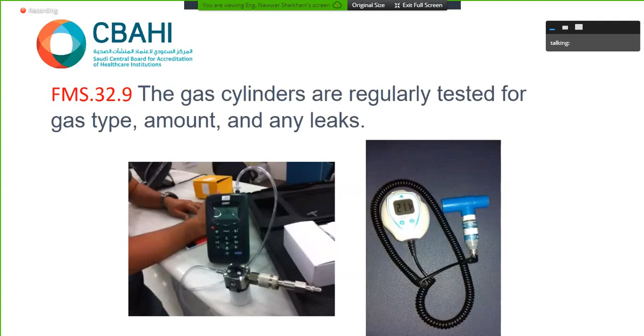Okay. We have explained to you why we should test regularly the cylinders we receive from the supplier, even though the cylinders have a tag. I explained that a few years before, we tested one cylinder with our medical gas analyzer, and we found that the Entonox cylinder was not 50% oxygen, 50% nitrous oxide. It was 48-48. That's why we informed the supplier, and the factory sent the tools to Italy for calibration, and sent us an appreciation letter with his apologies. So since then, we put this standard that once we receive a batch from the supplier, please randomly choose one cylinder and test it with an oxygen analyzer to know the type.